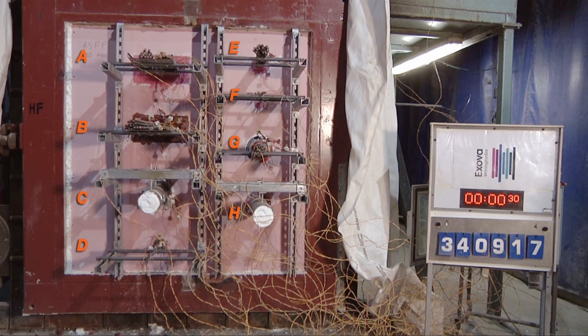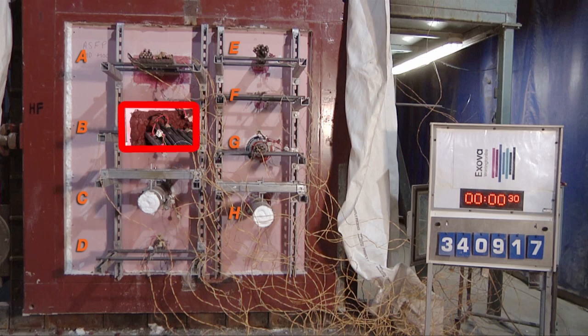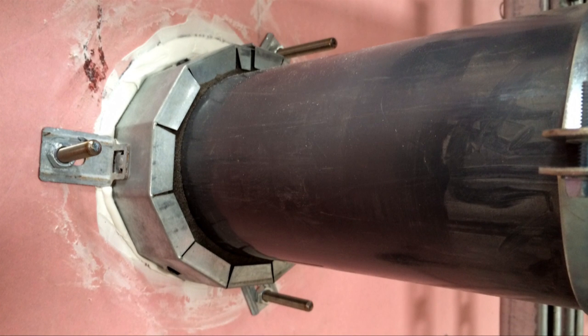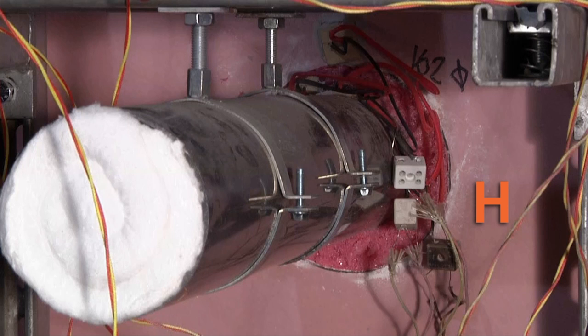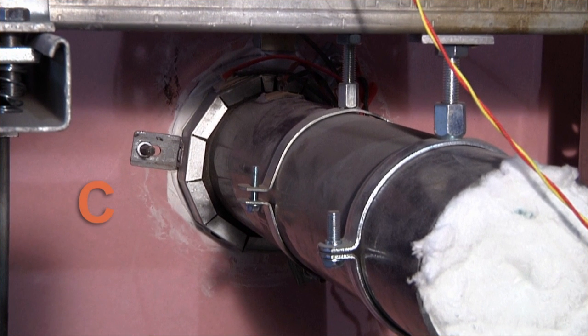The following scenarios were tested. For cable trays: A shows a foam inappropriately used to fire-stop a cable tray penetration; B is a similar cable tray penetration sealed using a foam with a proven fire-resistance performance for this type of application. For plastic pipes, it is essential that the fire-sealing system closes down the opening through the pipe as it melts. H shows a foam inappropriately used to fire-stop around a plastic pipe with no means of closing the opening. C shows an identical plastic pipe protected with a correctly installed, fire-resisting, intumescent fire-stop pipe collar.